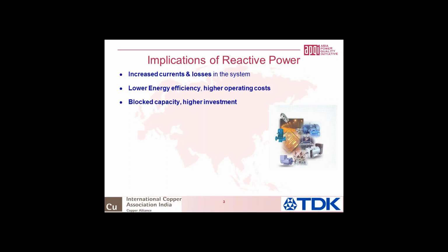Maybe this delivers only a 70, 80, or 90 kilowatt load, which means I need to rate the transformer for a higher volt ampere, which means a higher investment. And whenever we have losses in the equipment, you also have additional heating. As we know, for any electrical insulation, which could be a polymeric insulation or an oil paper insulation, whenever there's additional heating, the operating temperatures go up, which means there's a loss of life or a lower reliability.